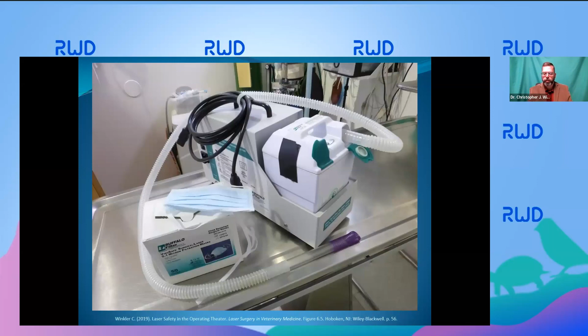Smoke plumes are a serious safety concern with lasers, particularly CO2. The CO2 laser vaporizes cellular water that can create carcinogenic plumes that can even carry live viruses. A smoke evacuator is thus an essential piece of safety equipment for laser surgery, and it should be held very close to that plume, as close as you can get it without breaking sterility. We also use a 0.1 micron surgical mask to filter any remainder of the plume that escapes the evacuator.